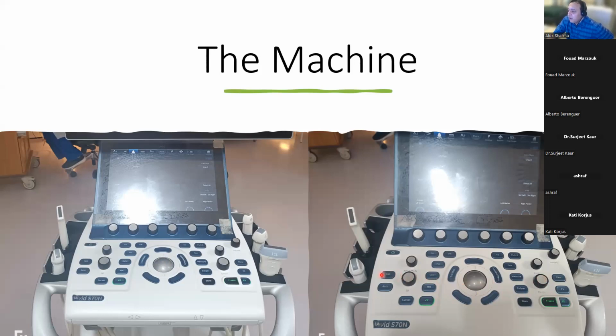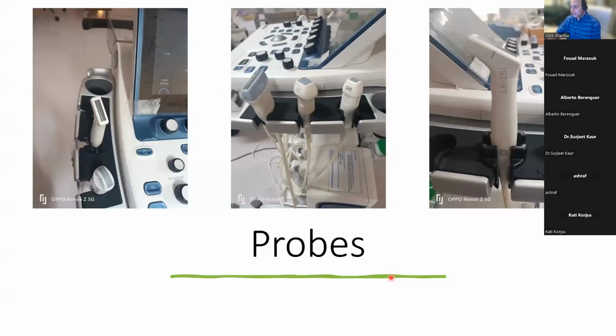So there is gain compensation, or what we call auto gain in some machines. Now, to get your gain settings right, if you have an auto gain function, you put probe gel, and this is very crucial. For a lung ultrasound, it's really important that you have gel that's uniformly applied throughout. So if you have gel over here and no gel over here, the way you interpret images and image quality will not be great. But more importantly, if you lose contact, then your interpretation will be affected.